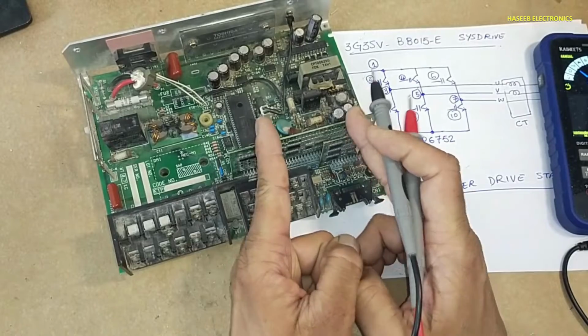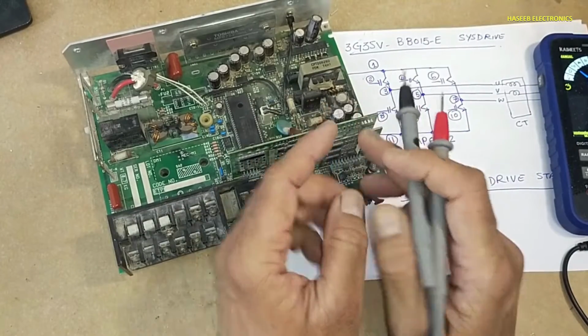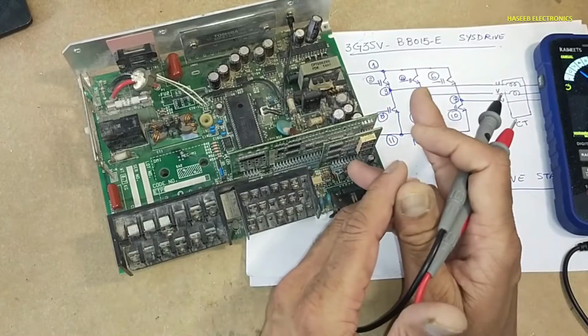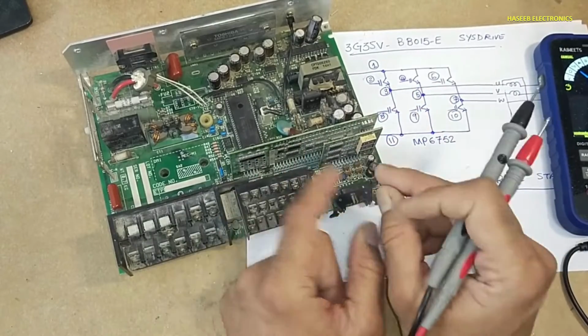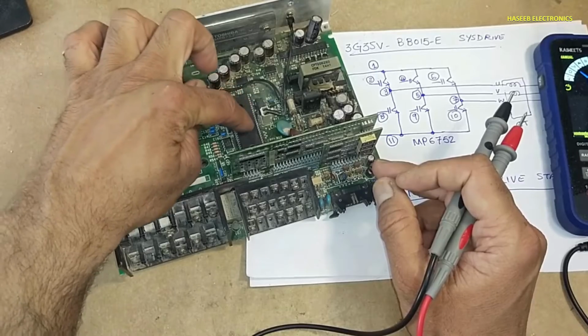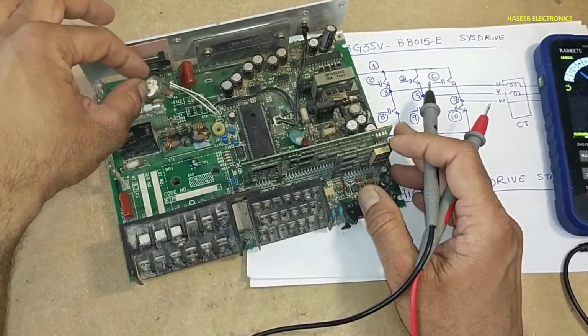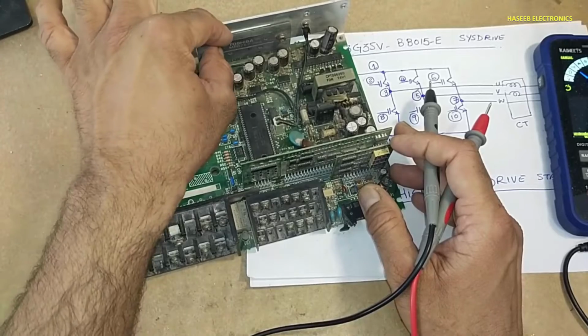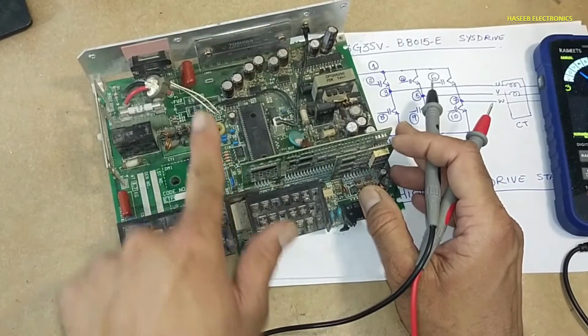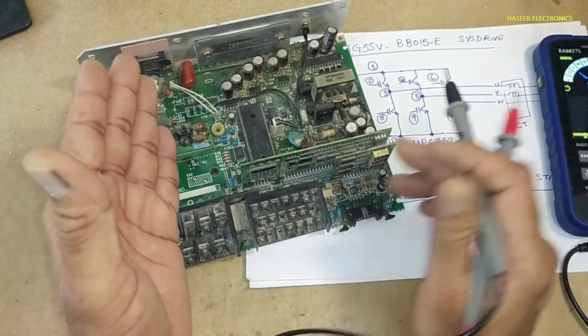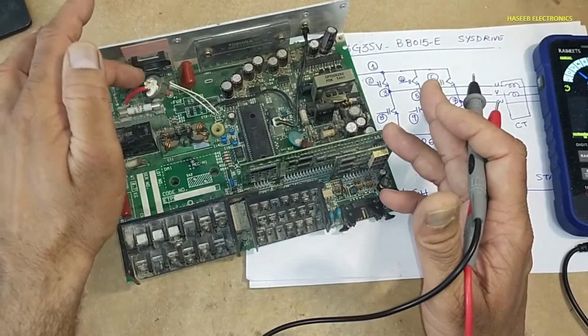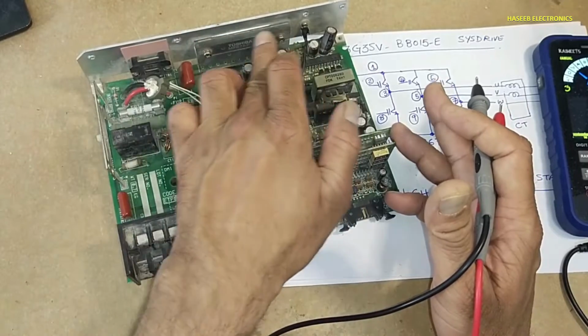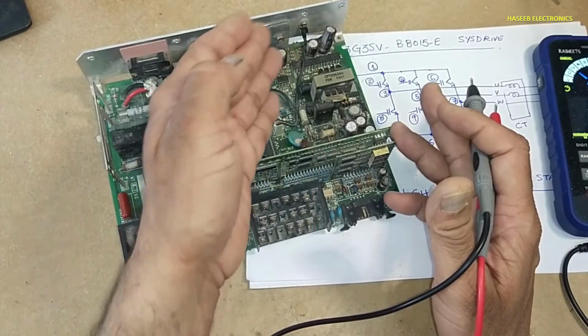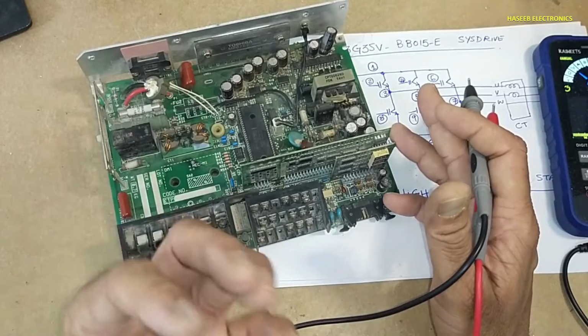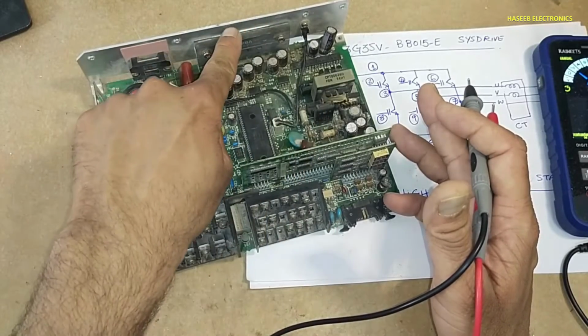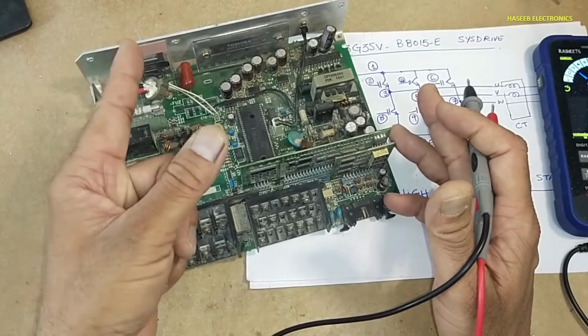So it will monitor input current and output current, and convert the equivalent voltage value into digital format to provide to this microprocessor, so that it will come to know how much current is entering this module and how much load is connected to this module. If there is any imbalance or high input current, that means this module is damaged. If overloaded, the load is drawing more current, that means this module may be damaged due to overload.